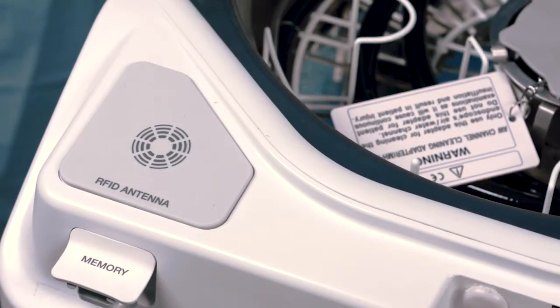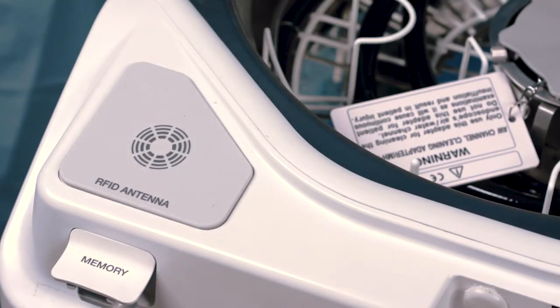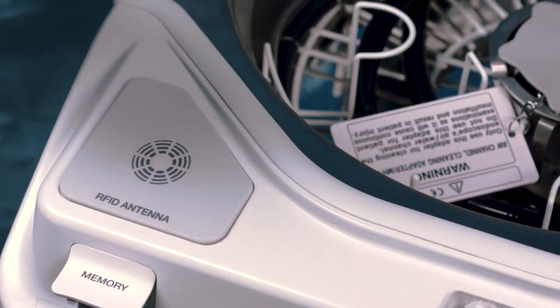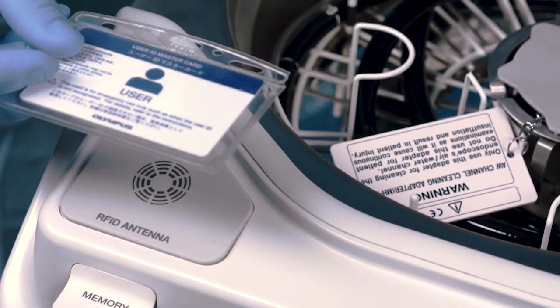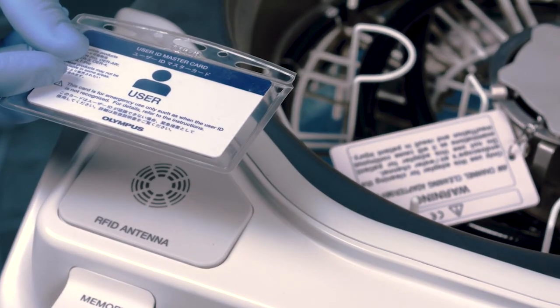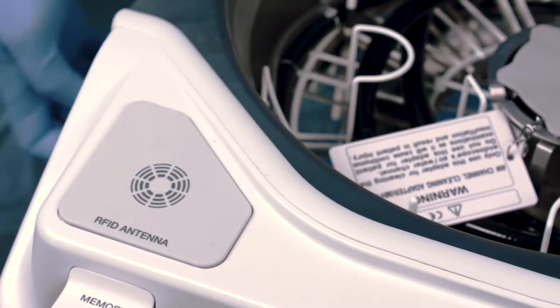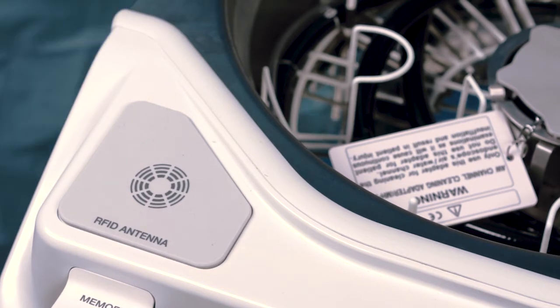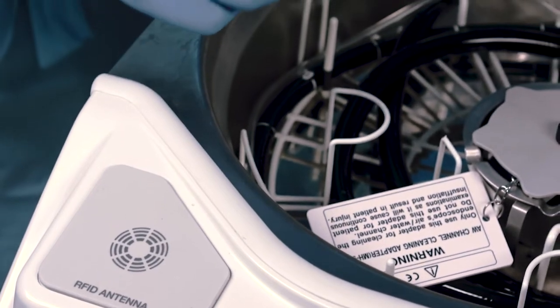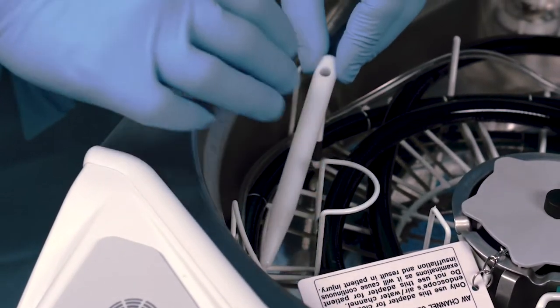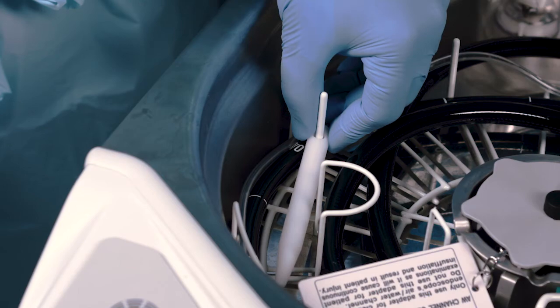Once you've confirmed the scope has been manually cleaned and leak tested, it's time to scan the user ID card. Just like when we scanned the scope's RFID in our reprocessing log video, we're going to scan the user ID card in the same manner. Simply hold the user ID card over the user ID reader section so that the OER-Elite can read the user information. The same can be done with the physician ID card. Then, set the stylus pen on the ring of the retaining rack.